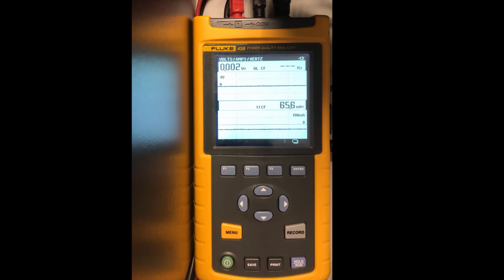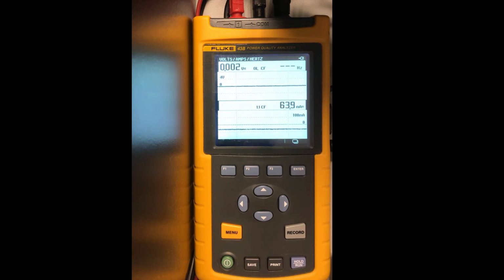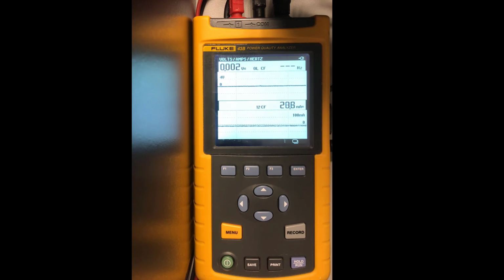So you can use that to help you understand which way you need to turn the wheel in order to bring it to 0. So in this case, because it's below, I'm going to turn it clockwise to bring it closer to 0. So that's what I'm doing right now, I'm adjusting this wheel and turning it clockwise this way in order to bring it closer to 0. Now, when you do this, you should keep the probe steady and not move it around, because you can see what happens if I move it around. I'm waving this thing around right now, and you can see how it's changing the current all over the place, and that's because it's sensing a changing magnetic field. So what I want to do is keep it steady, like I am.